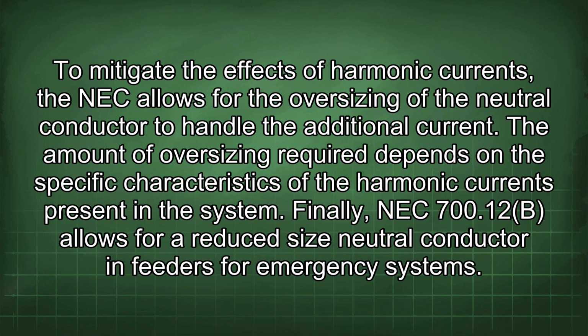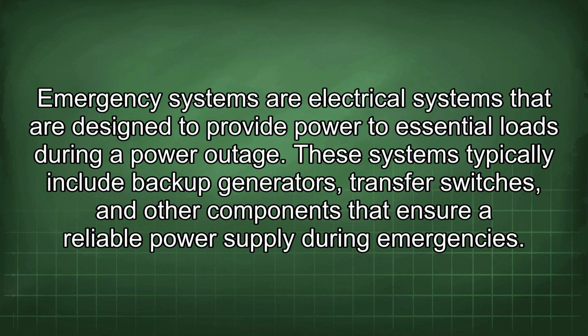Finally, NEC 700.12(B) allows for a reduced size neutral conductor in feeders for emergency systems. Emergency systems are electrical systems that are designed to provide power to essential loads during a power outage. These systems typically include backup generators, transfer switches, and other components that ensure a reliable power supply during emergencies.